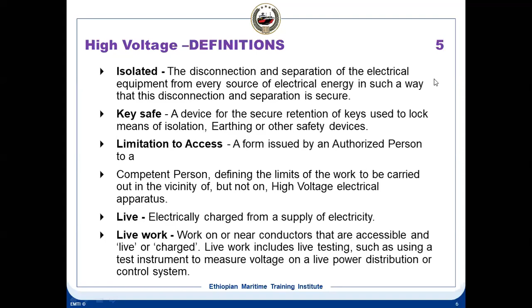Limited access: a form issued by authorized persons to a competent person defining limits of work to be carried out in the vicinity, but not on high voltage electrical apparatus. So what are the limits of work to be carried out? That's a limitation to the access. Live work means work on or near conductors that are accessible and live or charged. Live work means 440 systems, you can still work live. If you want to work live, there are procedures and permits for that. But in high voltage, live working is not allowed.